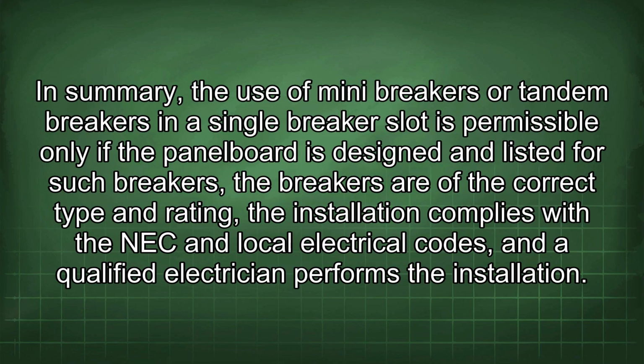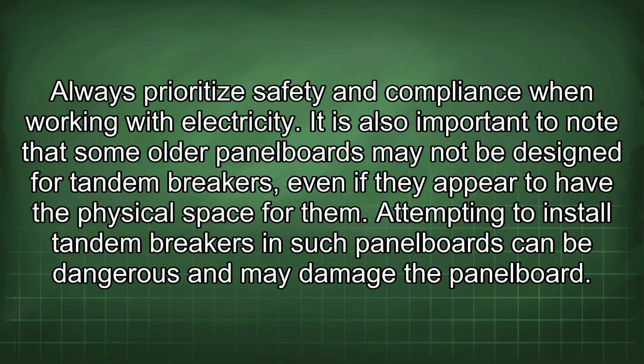In summary, the use of mini breakers or tandem breakers in a single breaker slot is permissible only if the panel board is designed and listed for such breakers, the breakers are of the correct type and rating, the installation complies with NEC and local electrical codes, and a qualified electrician performs the installation. Always prioritize safety and compliance when working with electricity.